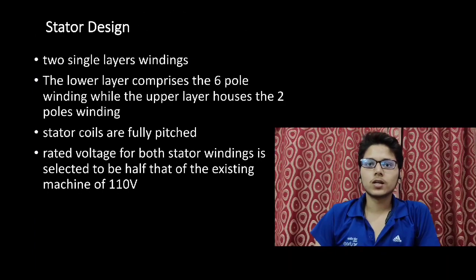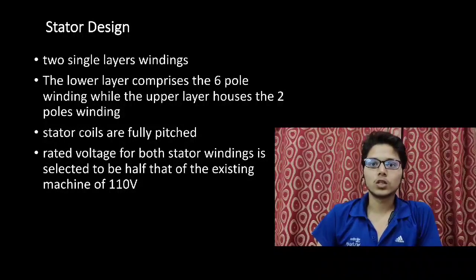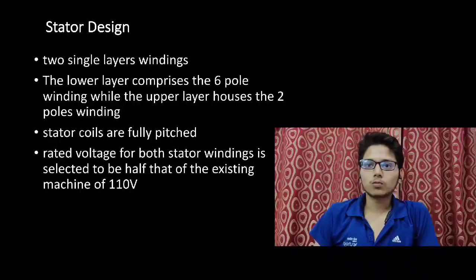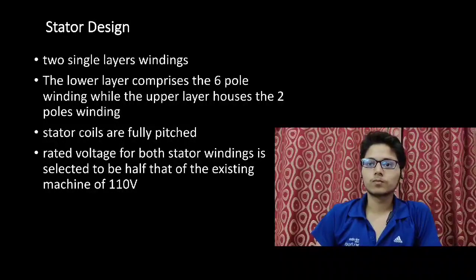Now let's move to the stator design. The stator is wound with two single layer windings. The lower layer comprises the 6 pole winding, while the upper layer houses the 2 pole winding. Since an existing stator is used, the only design criterion is the number of turns for each winding. The stator coils are fully pitched because each winding is wound with only one layer. For a total of 36 slots, the number of slots per phase per pole for the 6 pole and the 2 pole windings are 2 and 6.